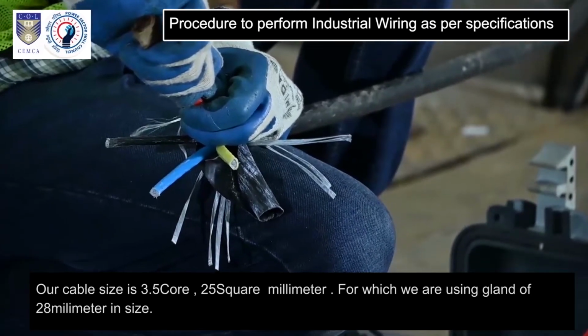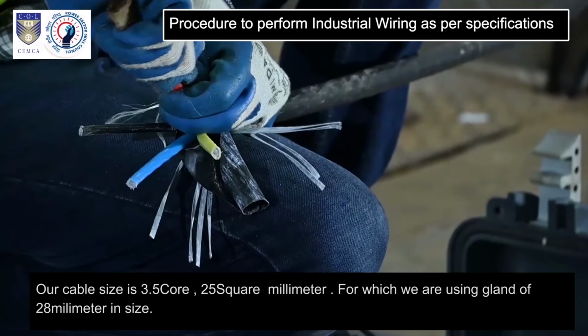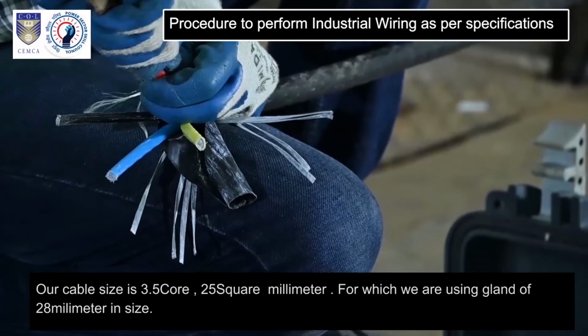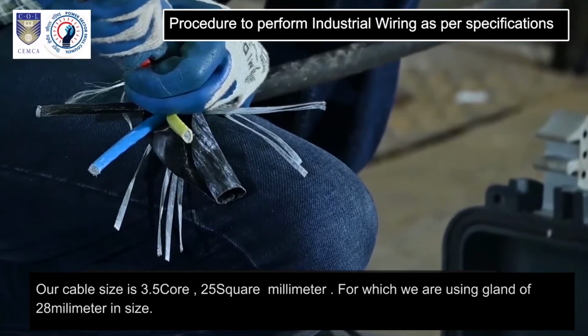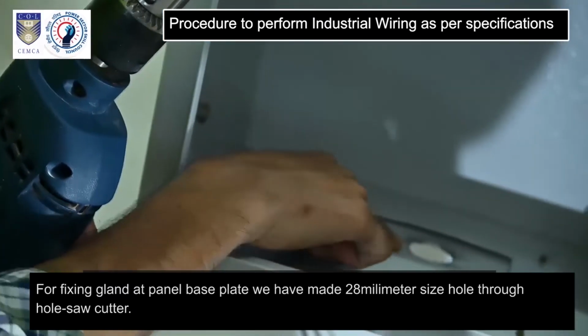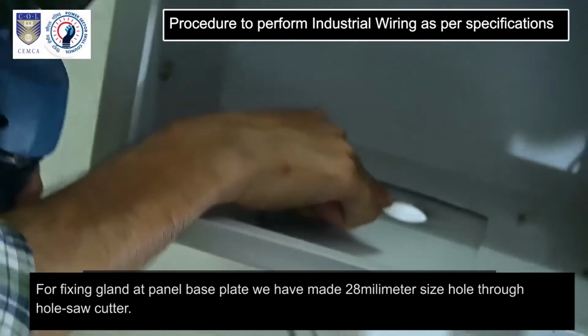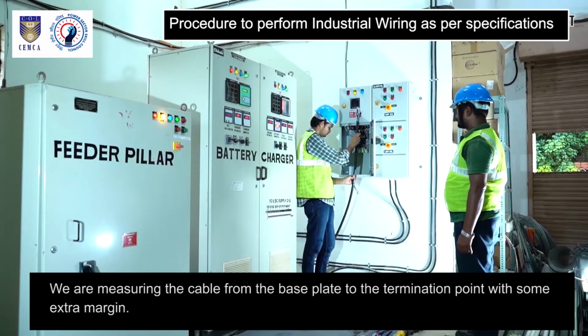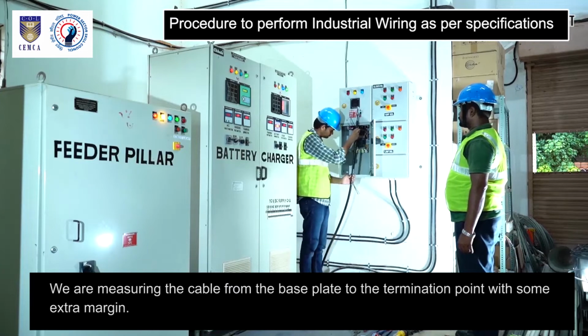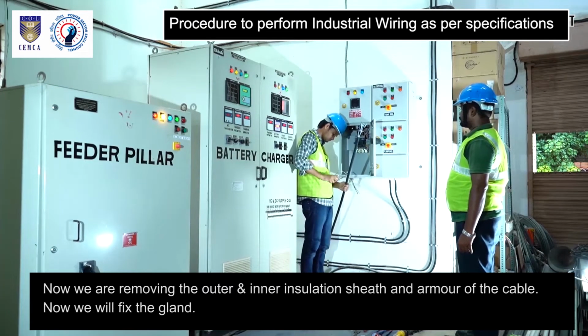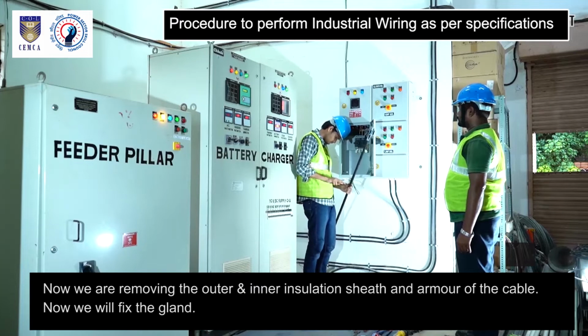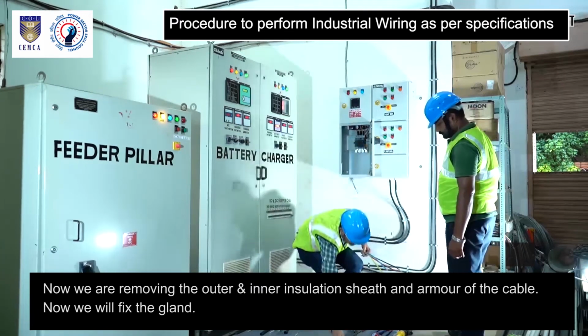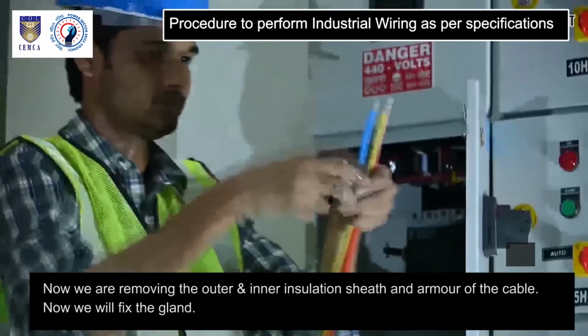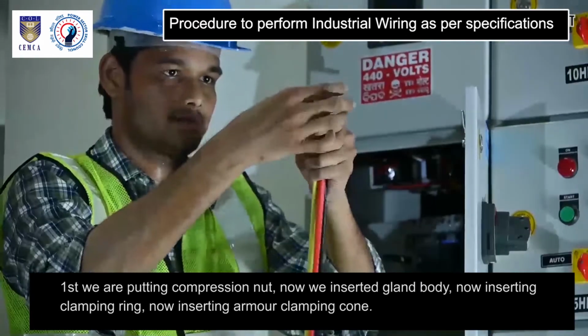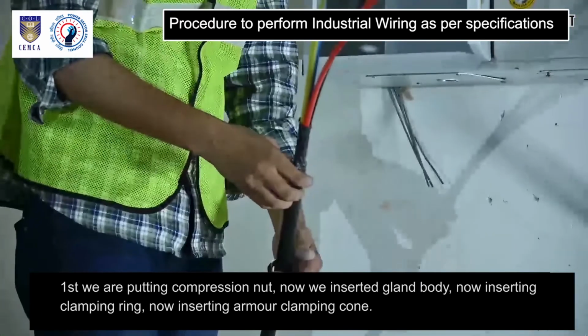Our cable size is 3.5 core, 25 square millimeter, for which we are using gland of 28 millimeter in size. For fixing gland at panel base plate, we have made 28 millimeter size hole through hole saw cutter. We are measuring the cable from the base plate to the termination point with some extra margin. Now we are removing the outer and inner insulation sheath and armor of the cable. Now we will fix the gland. First we are putting compression nut. Now we inserted gland body.